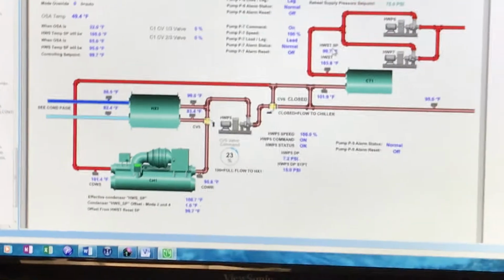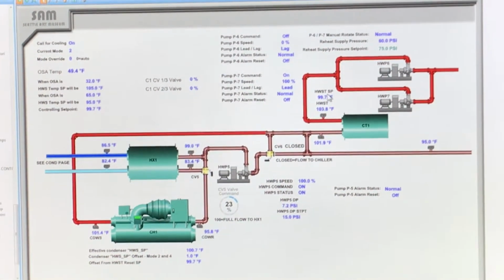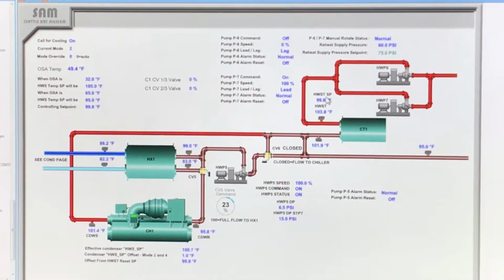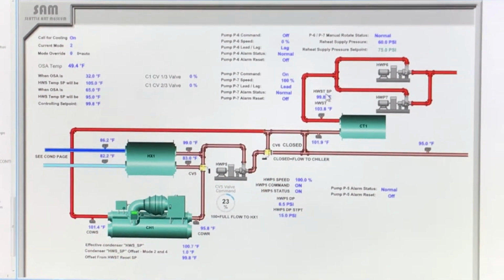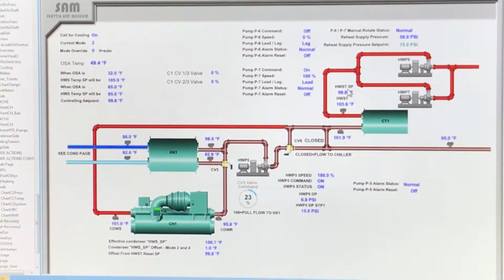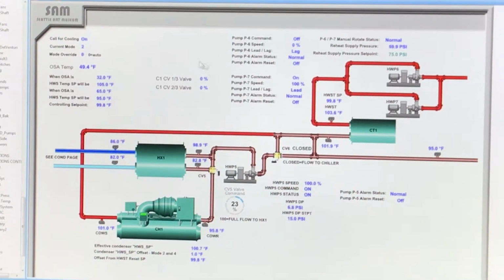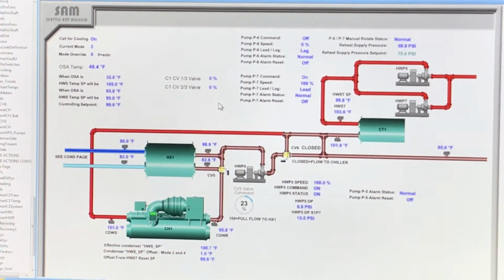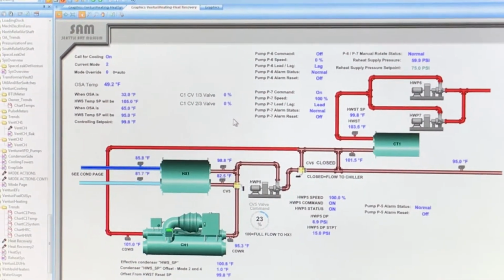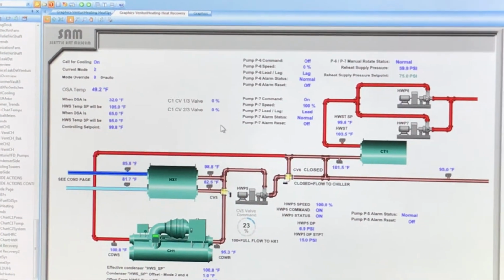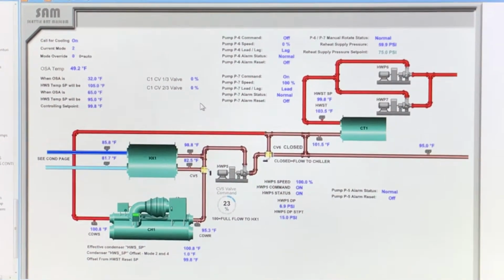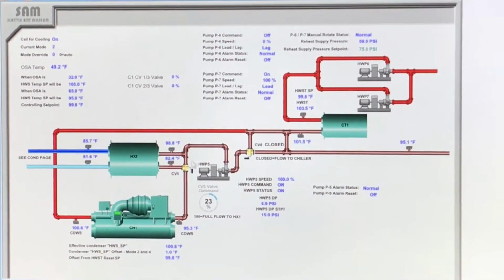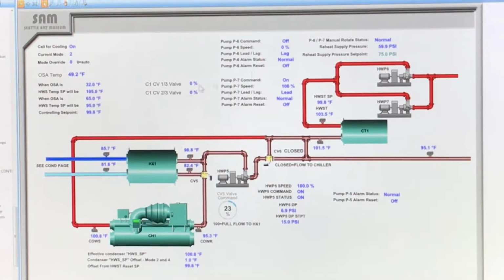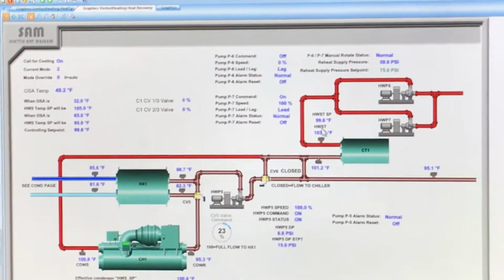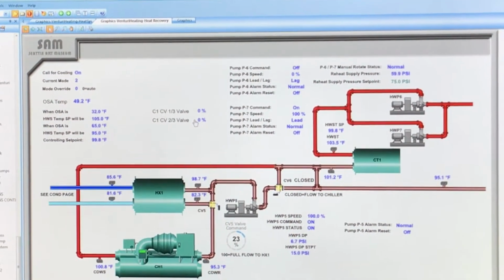Now, just to chime in, below that you're going to see we are actually supplying hotter water to that system, because all that really is doing is controlling to the set point for the steam valves. Isn't that correct? Yes, I think the one in the left-hand corner is controlling the steam valve. The steam valve will moderate to maintain your set point. However, the approach is that there is another sensor on the leaving condenser water temperature down below on that pipe. So right now this is controlling this temperature, and that is controlling these valves. So why are they not open?